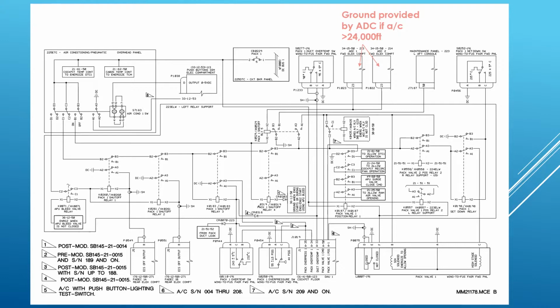Now we've got 2 FADECs there. It depends on which FADEC is in control of the engine at the time, and it doesn't matter because all these contacts are in series. So whichever FADEC it is, let's say it was FADEC 1A, which is the first box, when we advance the power levers and we're in takeoff 1, the FADEC will provide a ground signal causing that relay to energize. That means the pack will shut down. There's no more power going to the on solenoid. It de-energizes and it shuts.